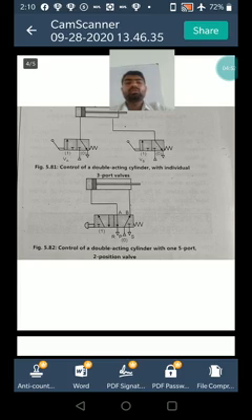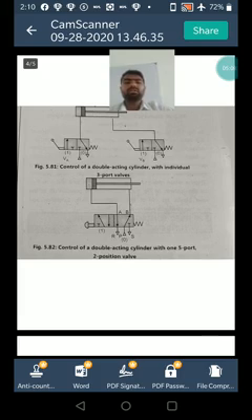Extension stroke of cylinder can be obtained by shifting valve VA to position one and air is admitted to the piston side. Since the rod side air is exhausted through VB position zero, the extension of piston is allowed.